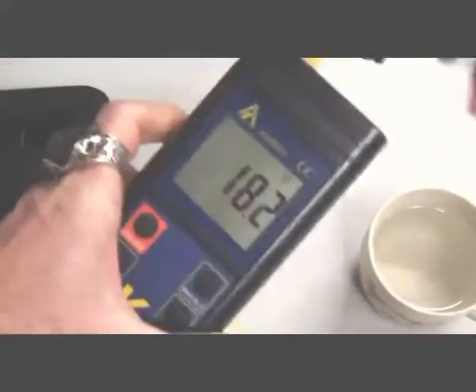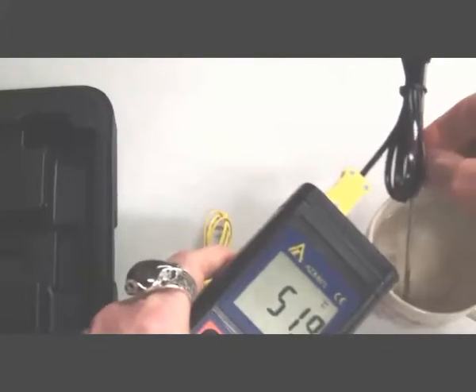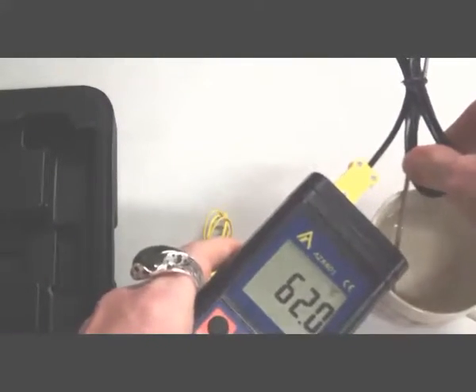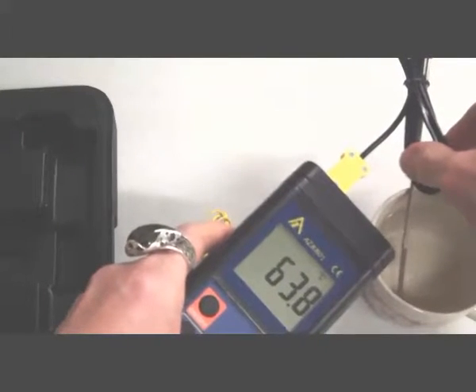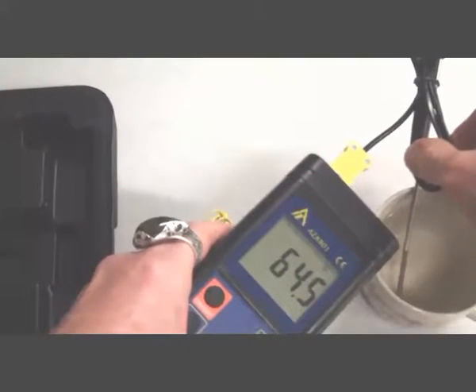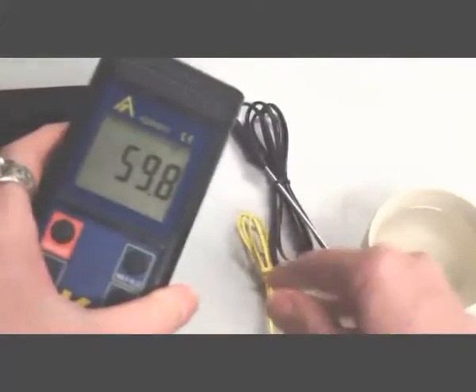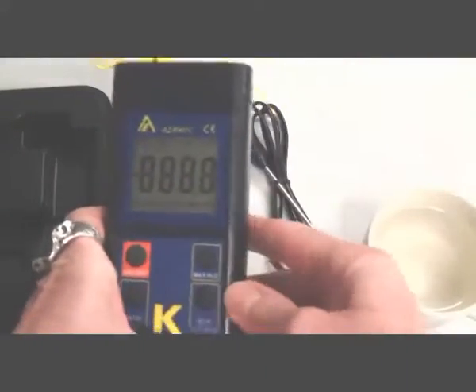Now, if I show you a stick probe, and this is a food grade stainless steel stick probe. If I plug that one in and put that one into the water, you can see it's reacting very quickly, but it's taking an extra second to actually count up the degrees of temperature. So this is the difference. The wire probe will react immediately to the changes in temperature, and the stick probe or any other stainless steel probe that you get won't react quite so quickly.